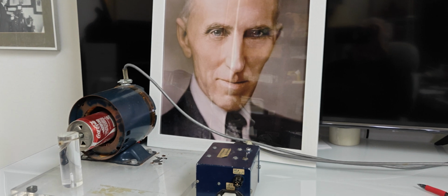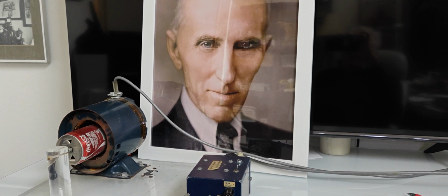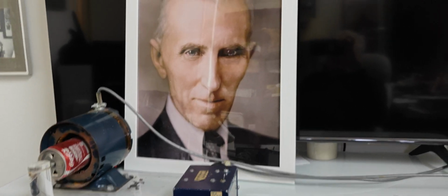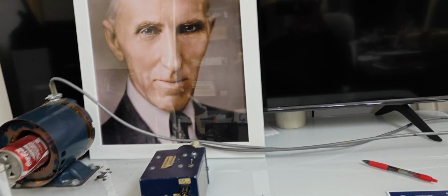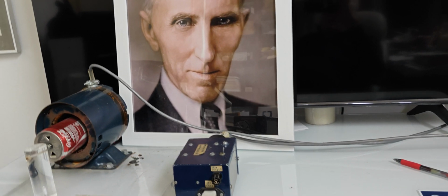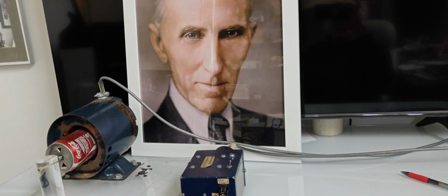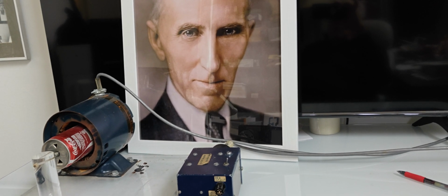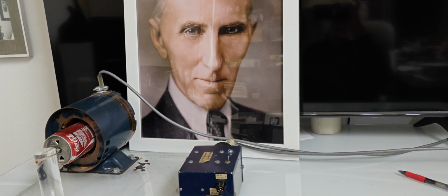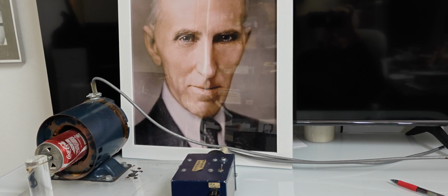How did we do that? Well, we faked it and made an almost good second-phase system by using the same utility line and putting a capacitor in series with it, a rather large capacitor, which will convert the current to make it close to 90 degrees shifted from the primary generating utility power.